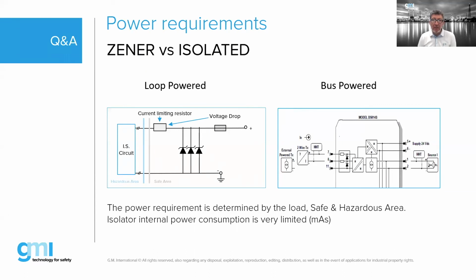Because the power, you either provide the power through the power supply externally or through the power supply inside the barrier. But at the end, you need to provide the power for the transmitter, and for the length of the wires, for your analog output or analog input card. So the difference is very limited. There is some extra power consumption on the isolated barrier, but it's not that much.